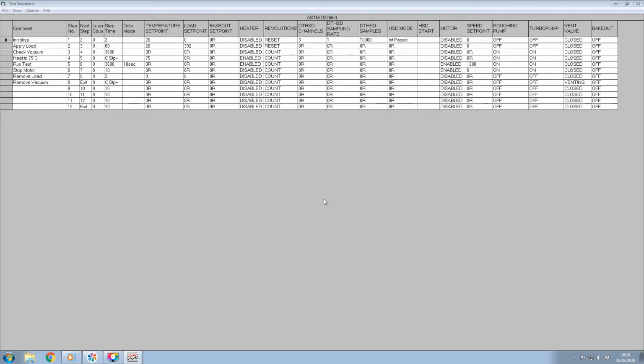In step 2, a load of 392 newtons is applied. You will see that the value 0R appears in many set point columns. This stands for zero relative. For example, the temperature set point for step 2 is given as 20°C. Right-clicking on the value will open a parameter box in which the value can be set to 0R. This means that there is no change relative to the set point in the previous step. So in this case, the temperature set point will remain at 20°C. The set point parameter box allows the user to switch between a relative value and an absolute value.